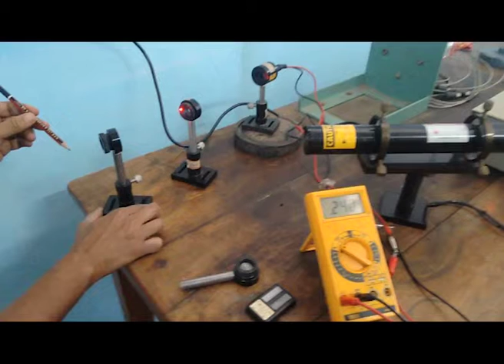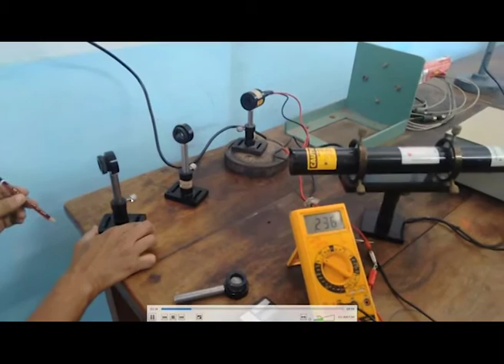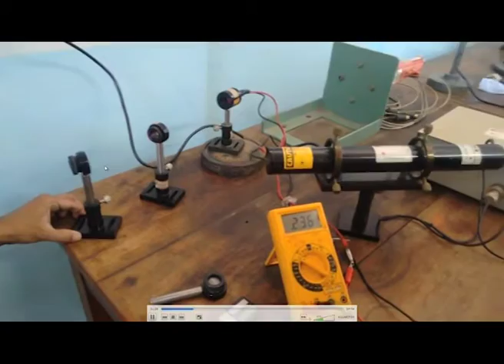So, once we calibrate the system using standard surfaces, we can inspect the surfaces whose surface finish is to be measured. Now you can see the angle we have to adjust so that the light will fall on this and then it gets reflected onto the detector. So now I am adjusting the angle. Now you can see the light is falling on the collimating lens and then it is falling on the detector.